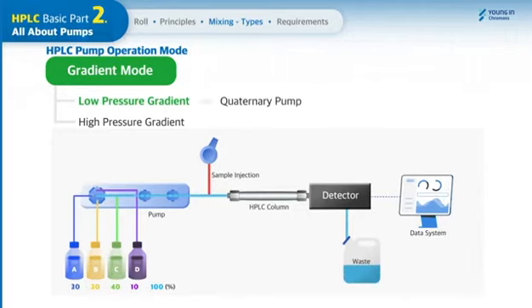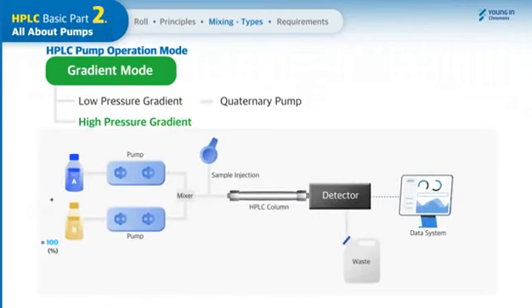quaternary pump. In high pressure gradient mode, 2 pairs of pump heads are required to draw individual solvents, and the mixer is placed on the next pump heads. You can utilize up to 2 solvents for mobile phases, and the pump used in this mode is called a binary pump. This mode is mostly used in the need of high productivity or high resolution HPLC, UHPLC applications.